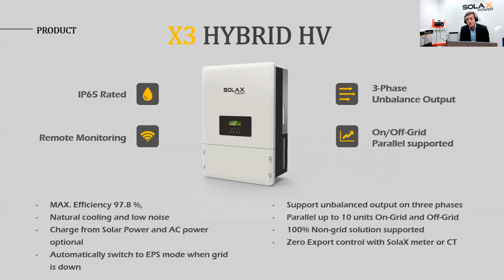To each inverter you can connect 4 batteries, with maximum 6.3 kilowatt peaks each, so almost 25 kilowatts of battery capacity per inverter. With 10 inverters at 10 kilowatt peaks of rooftop and 25 kilowatts of battery capacity each, you end up with 100 kilowatts roof energy and 250 kilowatts of battery. Combined like that, you can build a really big system.